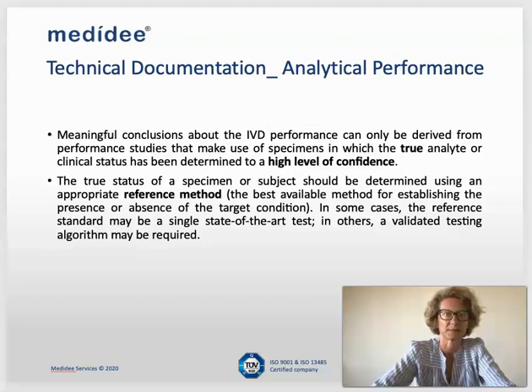One of the first steps when testing the analytical performance of the device is to be able to show that, independently of the specimen or sample type used, we will obtain the same measurement of the analyte or of the biomarker. For this, what is typically done is a matrix equivalency test in which, in parallel, we test the different specimen types that we are claiming, and we show that independently of the matrix used, we obtain the same measurement of the analyte or biomarker. Additionally, we need to show that our samples are stable independently of the matrix used during sample collection, processing, and also storage.